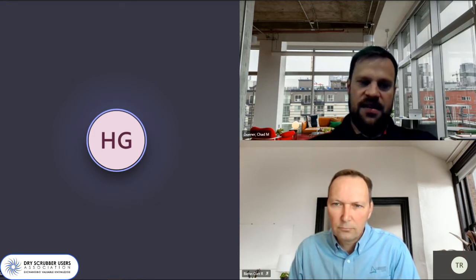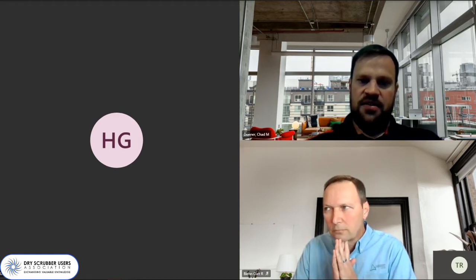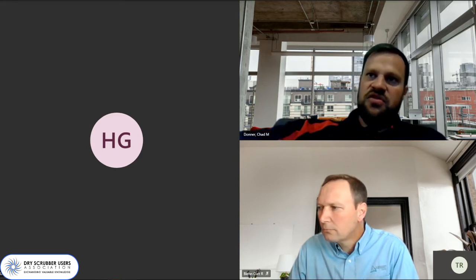Yep. I think that's where having your dew point and relative humidity monitoring in the system is critical. If you've got an upset with that dryer, you're going to see either a step change or a gradual increase over time. So trying to maintain that, and that's obviously trendable on a PI data system or whatever your data logger is. I think having that dew point indication in your conveying system is critical just for system health overall. And you can correlate that to pluggage events that you may have, where you may have issues or not have issues.